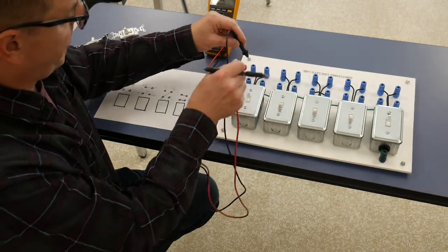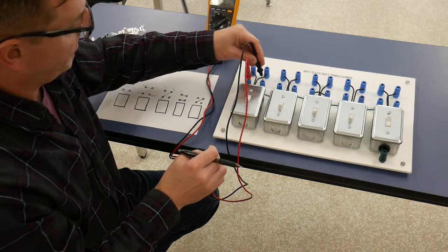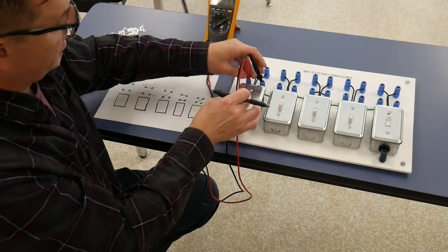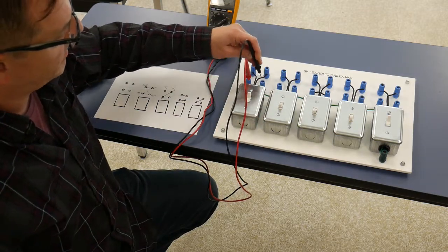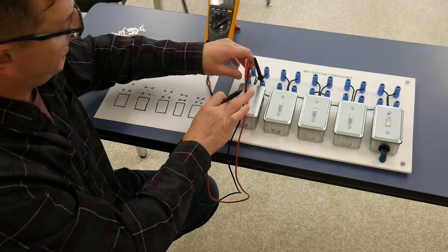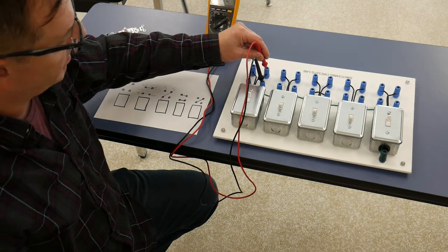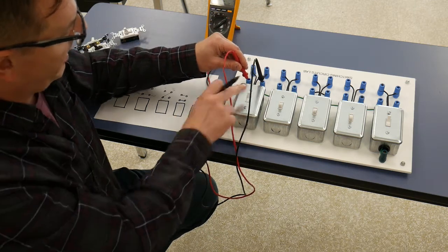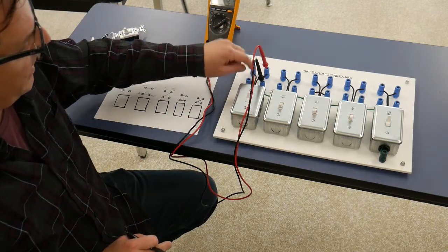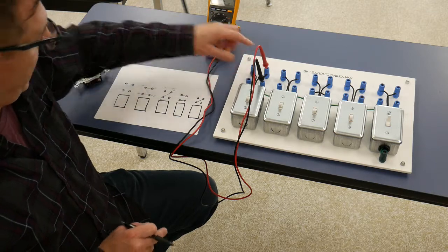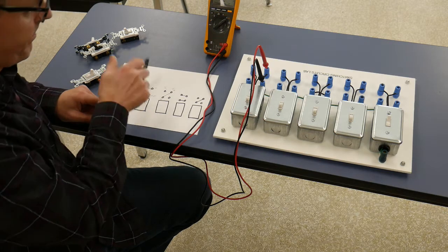Okay, next, my last 3-way. This should be my final 3-way. No beep there, no beep there. Oh, we got a beep there. Turn it to the other position. I'm going to keep that in that spot and see if I can find my common. So that's not correct. So I know we had a beep there, so I'm going to leave that black probe where it is, and then I'm going to go here and find another beep. Okay. So we had a beep on the lower and a beep on the upper in the other position. Black is my common on that spot, and these are my travelers here. So this is my common, my T1, my T2.